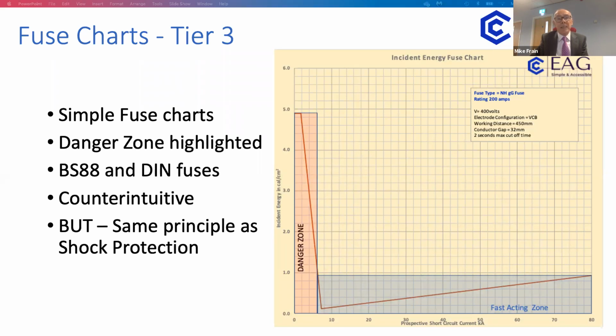But the other thing is a danger zone. It also tells you on the left-hand side that the pink block there is where it's below 6,000 amps, so it will take longer to clear, up to a maximum of 2 seconds. That's the sort of incident energy level that you could be getting in that particular case. So it's based on the same principle as shock protection. You need so much prospective short circuit current to operate overcurrent protection to reduce the time to trip to as low as possible.